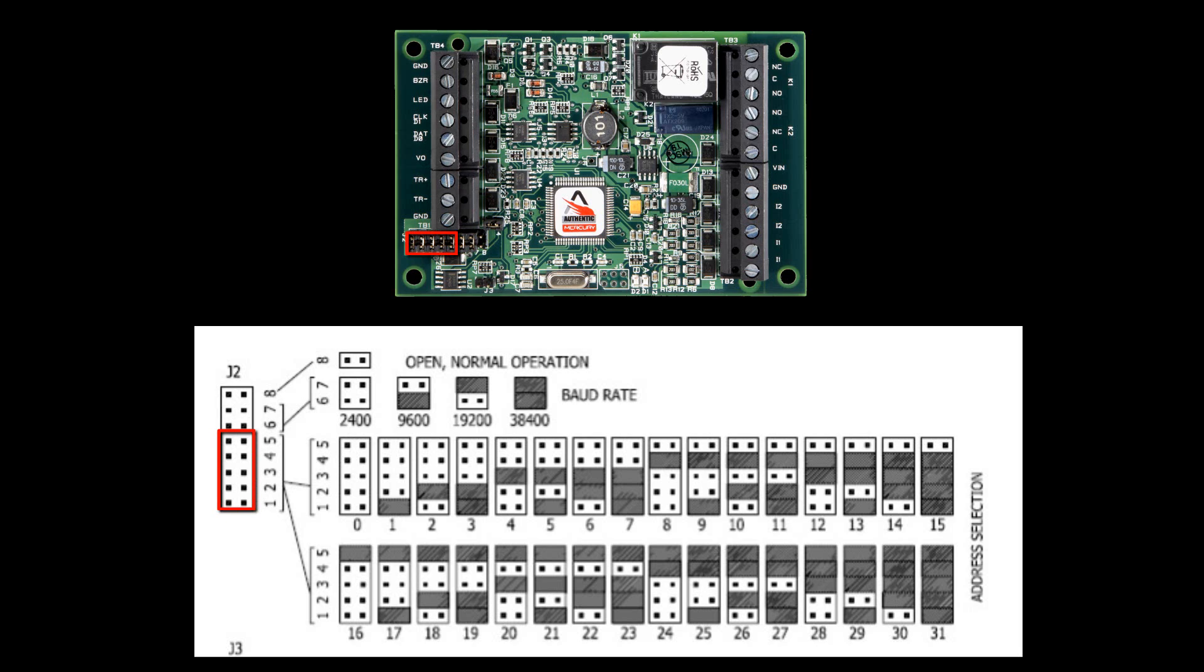Jumpers 1 through 5 are used to address the panel. J1 is 1 bit, J2 is 2 bits, J3 is 4 bits, J4 is 8 bits, and J5 is 16 bits. So, in our case, if we wanted the MR50 to be addressed 5, we would jump 1 and 3, because 1 is 1 bit and 3 is 4 bits, totaling 5 bits.